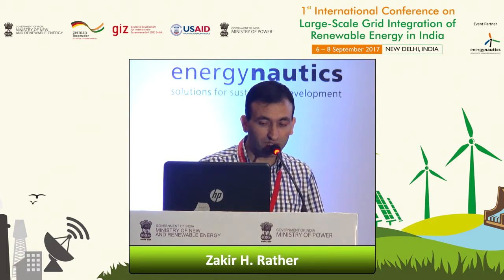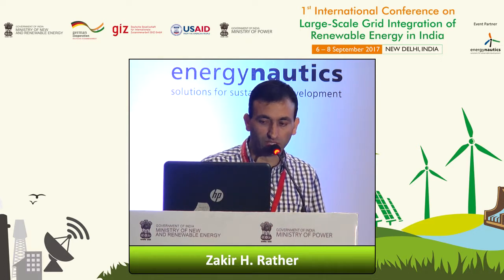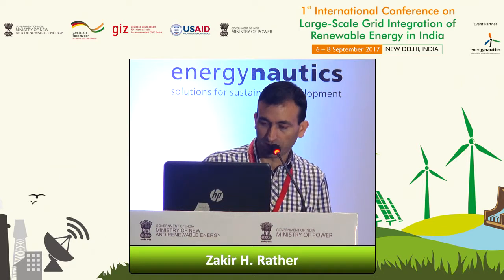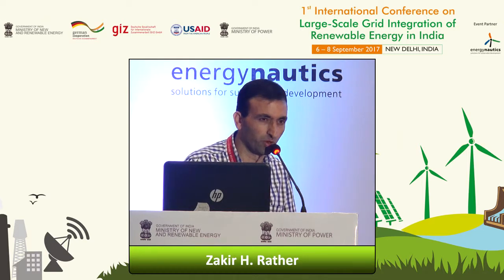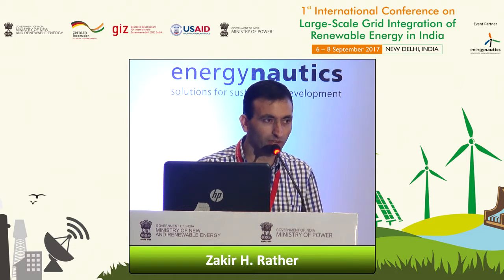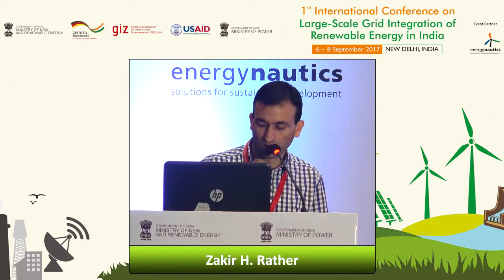In the very first base case, we didn't have inertial or droop capability in the wind turbines. If you see, the active power following the fault is going down in one of the wind farms, and as a result of that temporary shortfall in generation, it results in a frequency event in the system. The system recovers because of the headroom of the conventional power plants, and as it is a temporary shortfall, the generation eventually comes back to its nominal value. The synchronous machines have sufficient headroom to cope with this and recover back to the nominal frequency.